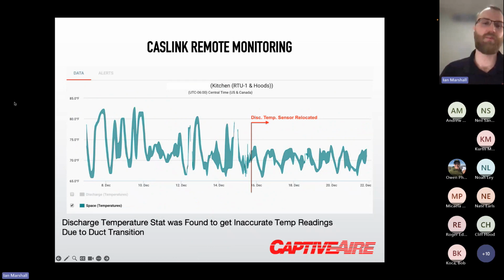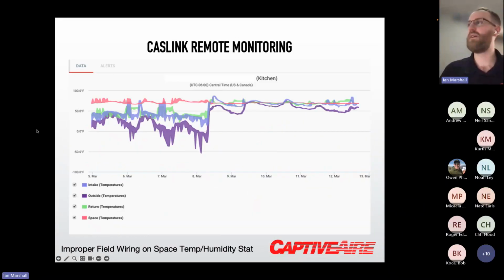This one, which is probably not an issue really anymore, was a downstream duct mounted temperature and humidity sensor that was installed on like an elbow of a duct, and it wasn't giving an accurate reading. It was getting some temperature spikes, which the unit wasn't able to control to an exact discharge temperature because of that. So they relocated the downstream duct temp sensor, and the discharge temps came into line and started looking a little bit more consistent.